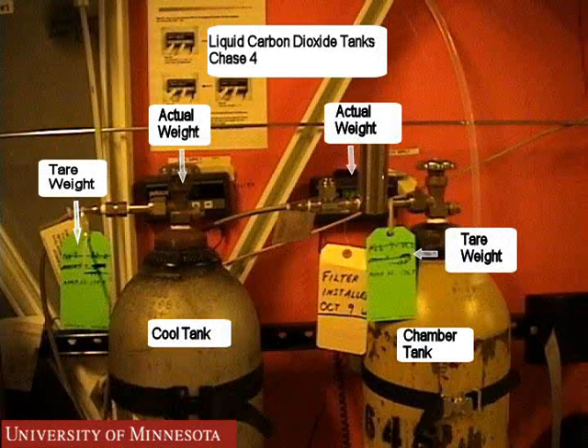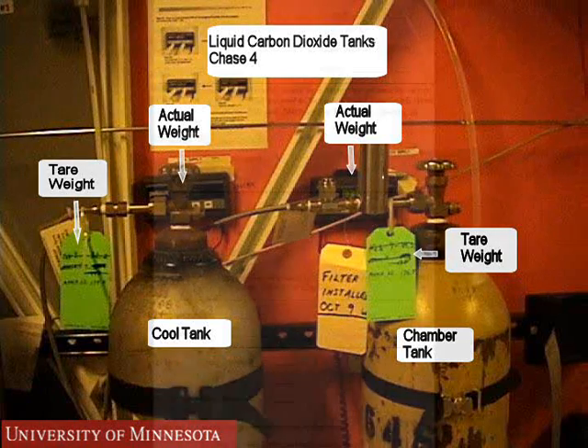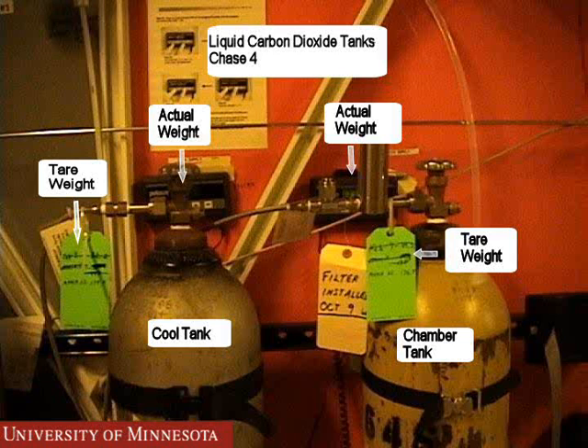Before using the CPD, verify there is enough liquid CO2 in the tanks behind the machine. The CPD log sheet has a place where the amount of CO2 remaining in the tanks can be calculated. Take the log book and go into the chase. Record the tare and actual weights for both the cool and chamber tanks. If the difference in tank weight is 30 pounds or less, the CPD can be used. If the difference is higher than 30 pounds, do not use the CPD. Contact the NFC staff member responsible for the equipment. When the tanks have been changed, the run can be continued.